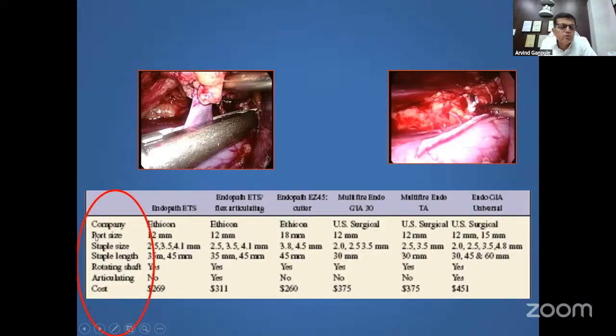Again, a very important point, you have to always see what is the port size that it accommodates. A few staplers, for example Endopath EZ45, that particular stapler will only go through an 18 mm port. So no point in placing a 12 mm port for that. So always see which port will accommodate which sort of stapler.